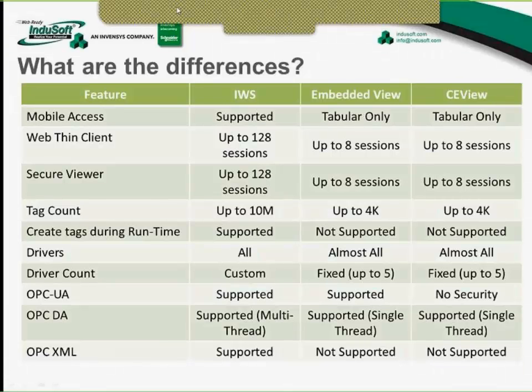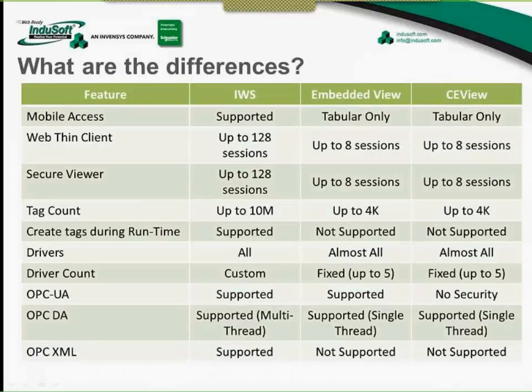Now, create tags during the runtime. That's supported by InduSoft Web Studio, but it's not supported by embedded view or CE view. And that's also a very interesting feature. With version 7.1, we created built-in functions into the product that you can use to create tags during the runtime. And a lot of customers, especially the ones working with machine builders, are using this capability. Because with that, you can develop a generic application where the customer can configure how many pieces he has in the machine, how many sensors, or any configuration that you might want to add, and you can create the tags automatically. And once you create the tags, the customer will know which license type he needs. So developing your application is of course more complex, but to be as generic as that, InduSoft Web Studio has that option. And it's not supported by the embedded view and the CE view.